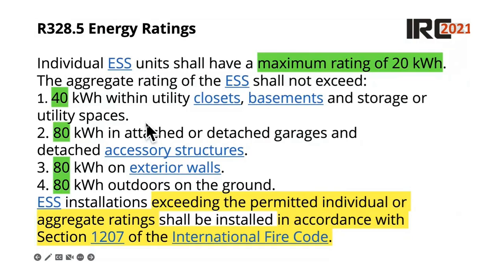And so let's move on to here. So we're looking now at the energy ratings, and individual units shall have a maximum rating of 20 kilowatt hours right here. And of course, if we did large scale fire testing, like is often done, we don't have to comply with this. And so the individual units, 20 kilowatt hours, and then the aggregate ratings of these units shall not exceed, so we could go 40 kilowatt hours in your utility closet or basement, storage or utility space.